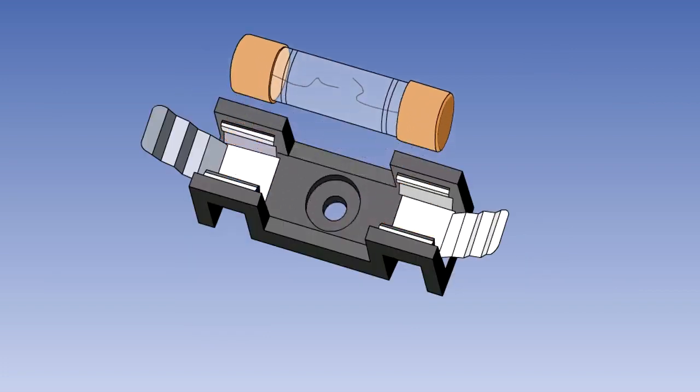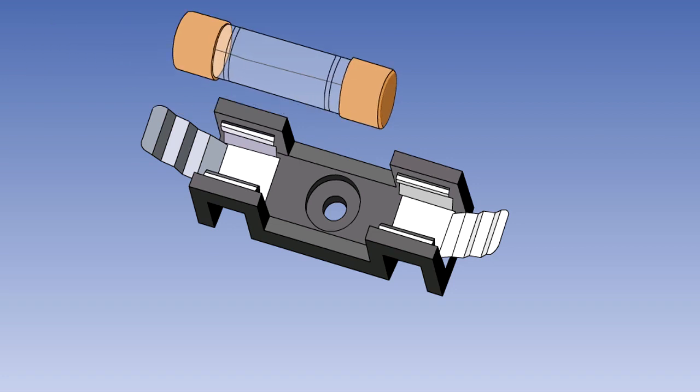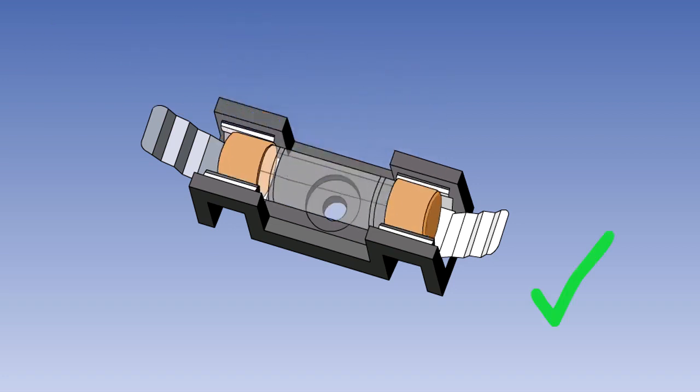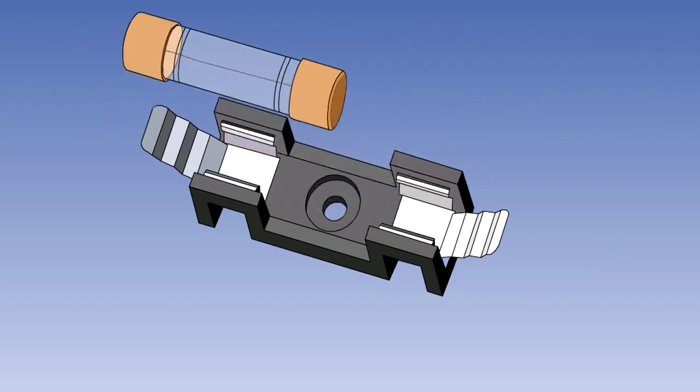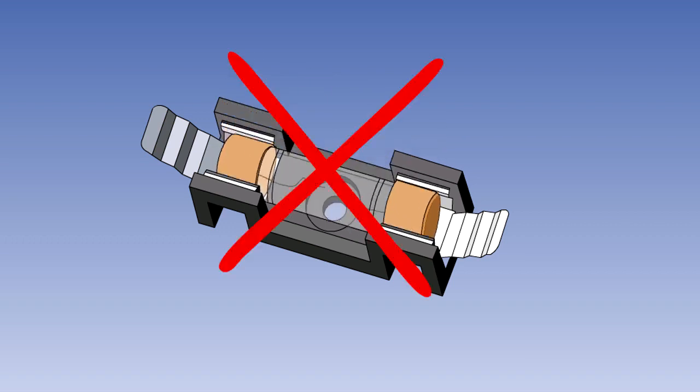A fuse once blown must be discarded and replaced. This should be done once only. If the fuse blows again, the fault must be investigated and corrected before a further replacement fuse is fitted.